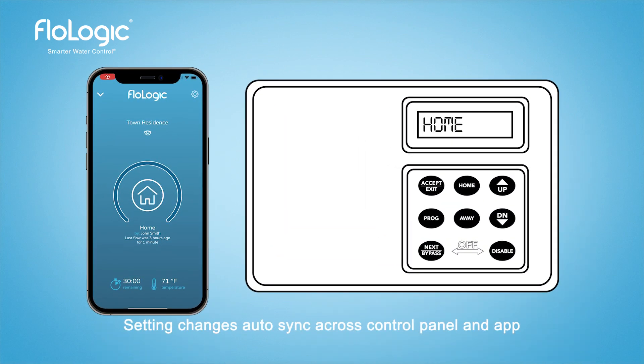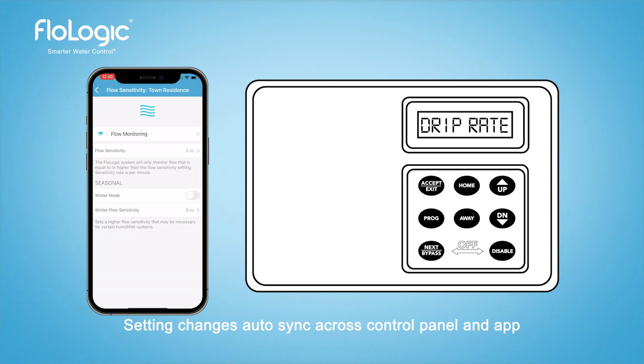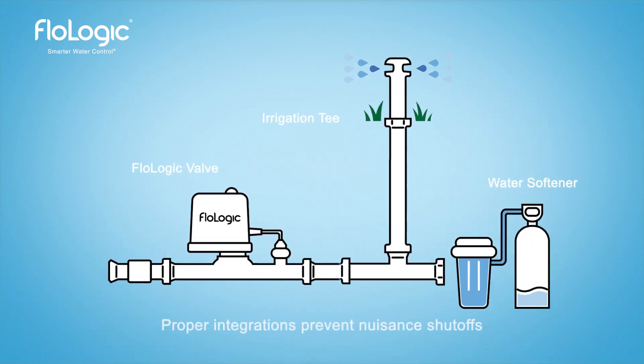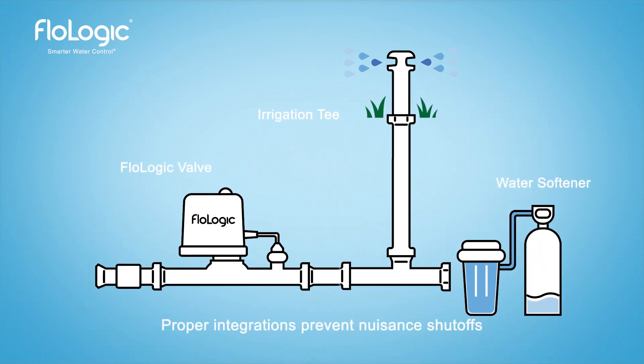You should also rule out water flow requirements that aren't leaks but could trigger auto shutoffs. Some appliances like humidifiers require an ongoing small trickle of water that requires raising the flow sensitivity setting. Irrigation systems and water softeners with backwash cycles can trigger auto shutoffs only if they are installed downstream of the FloLogic system without being integrated properly per the installation instructions.